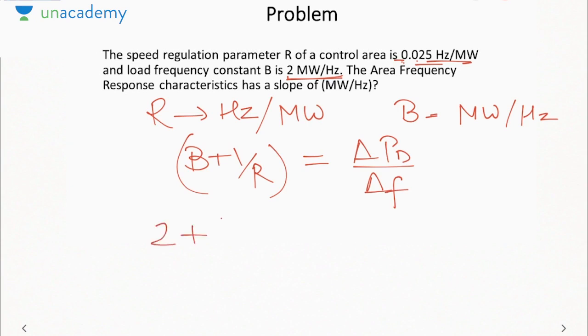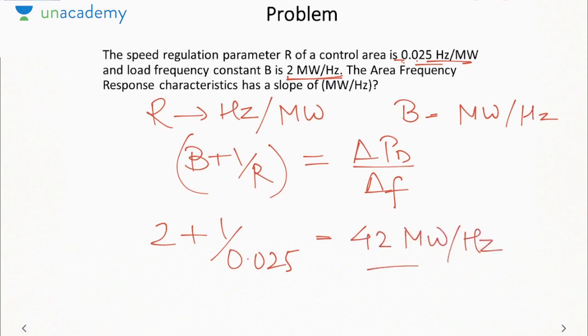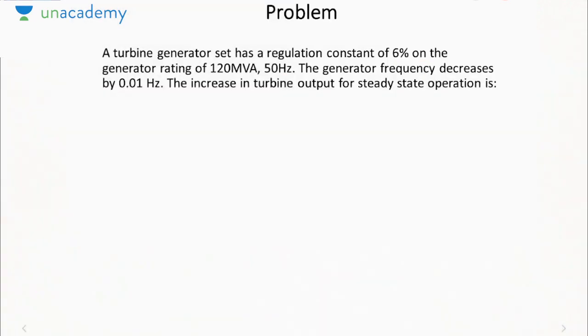So it will be 2 plus 1 by 0.025, which is 42 megawatt per hertz. That is, by changing 1 hertz of the frequency, the change in demand will be 42 megawatt. Moving on to the next problem.